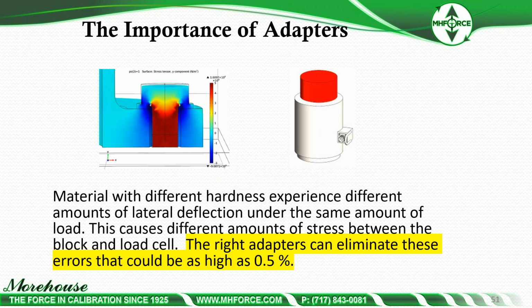More on the importance of adapters, which a lot of people tend to not realize, because they send us their load cells without top or bottom adapters, and that can be problematic. The reason it can be problematic is material with different hardness experiences different amounts of lateral deflection under the same amount of load. This causes different amounts of stress between the block and the load cell. The right adapters can eliminate these errors that could be as high as 0.5%.